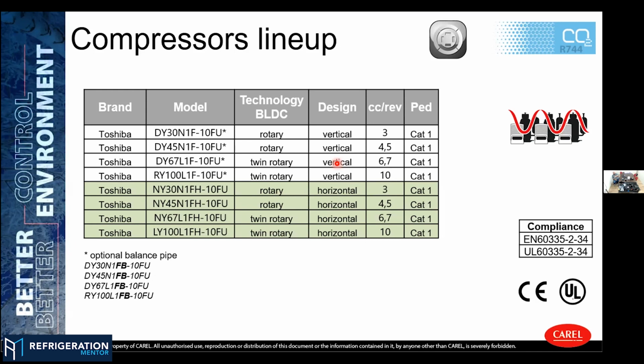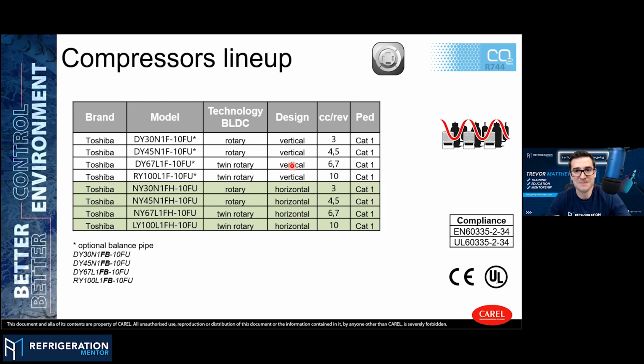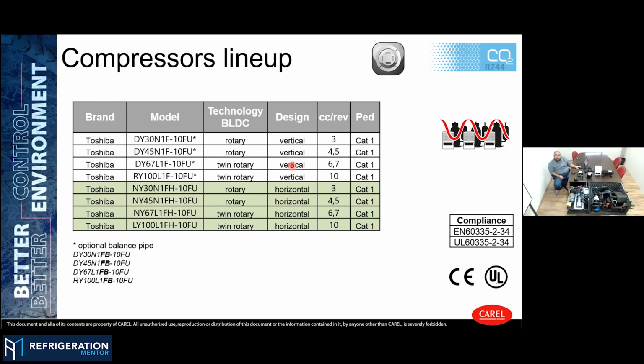And for each type of application, if transcritical, for sure the current absorption is higher, so it is the standard models. And if subcritical applications, we can try to downsize the inverter a little bit if it's possible. So we can make some adjustments in terms of inverter matching according to the application of the customer. This is a very interesting point. These compressors are UL certified to run both in subcritical and transcritical applications. And also in the UL, we have the match between inverter and compressors.